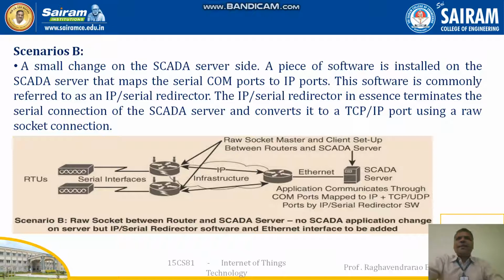The second scenario is a small change on the SCADA server side. A piece of software is installed on the SCADA server that maps the serial COM ports, communication ports, to IP ports. This software is commonly referred to as an IP serial redirector. The IP serial redirector in essence terminates the serial connection of the SCADA server and converts it into a TCP IP port using raw socket communication. There are serial interfaces, the IP infrastructure, where the raw socket master and client setup is between the routers, and the SCADA server is existing.